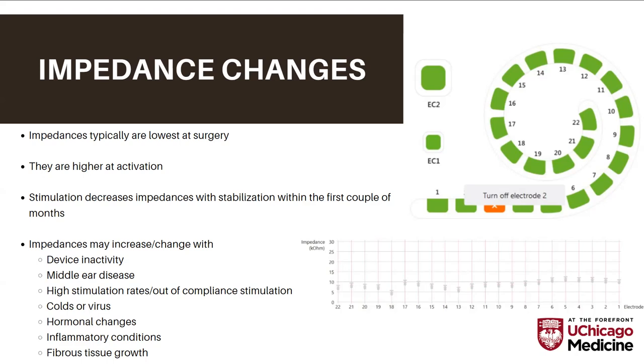Inflammatory conditions may cause fluctuations of the impedances. You may also have fibrous tissue growth — for example, in an explant re-implant situation, a fibrous tissue develops over the array, and if that is torn, it may shift the impedances. Other things to think about: when patients develop bacterial meningitis, there can be some ossification that occurs. There are a lot of things you can learn about the patient's overall hearing situation simply by checking this measure — and it's the first thing you'll always do.